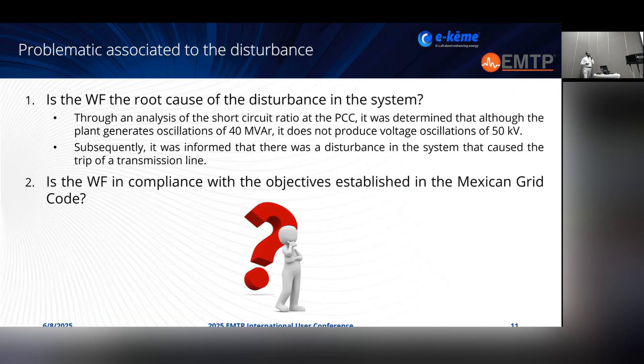So there are some questions that we can ask ourselves. Is the wind farm the root cause of the disturbance in the system? Well, we made an analysis of the short circuit power ratio at the point of common coupling, and it was determined that although the plant generates oscillations of 40 megavars, or is capable of generating them, it does not produce voltage oscillations of 50 kilovolts.